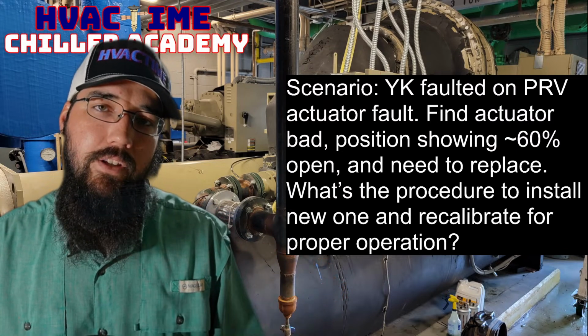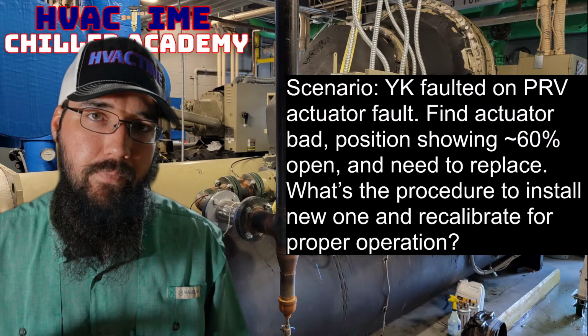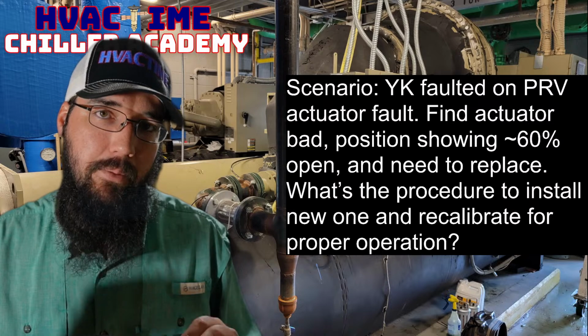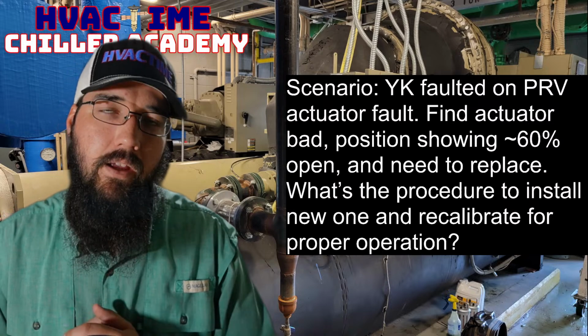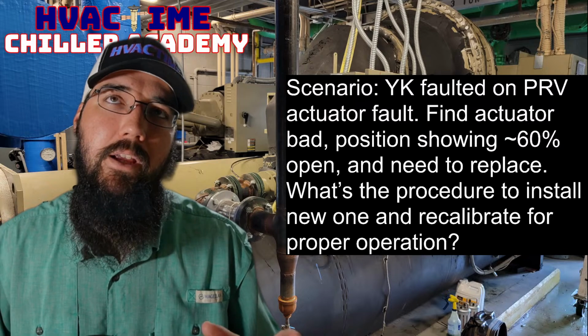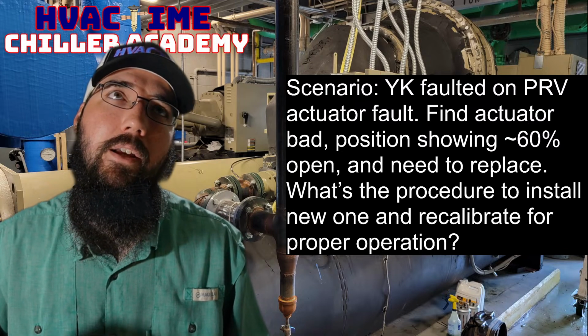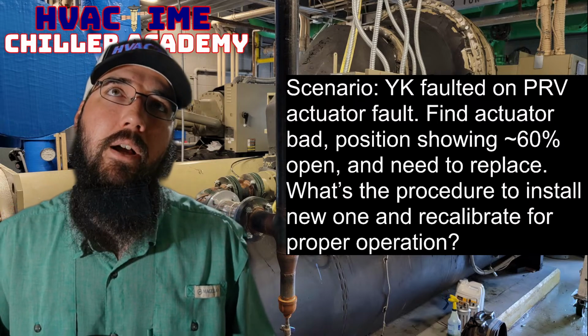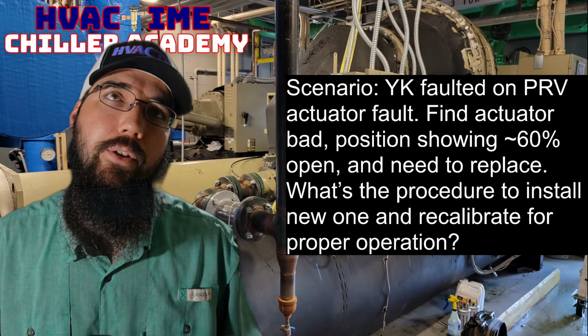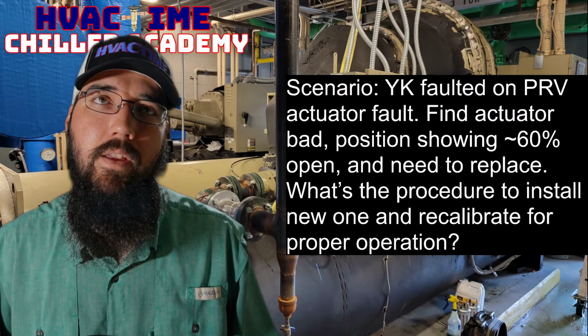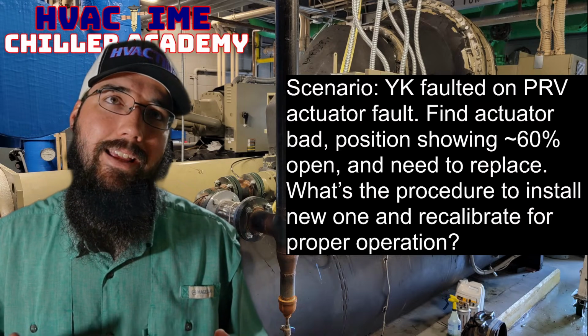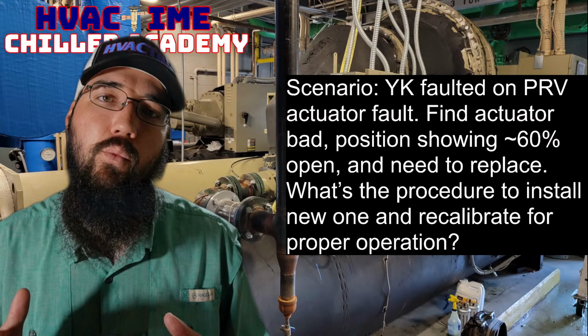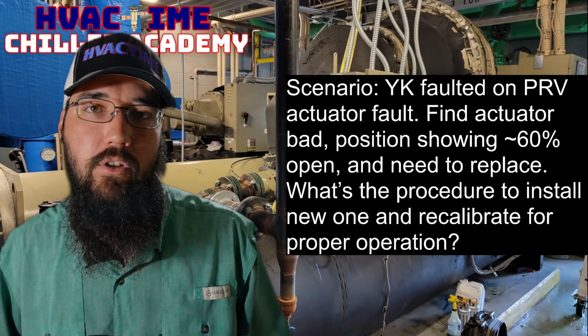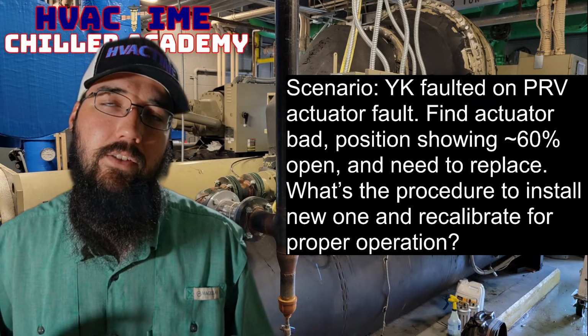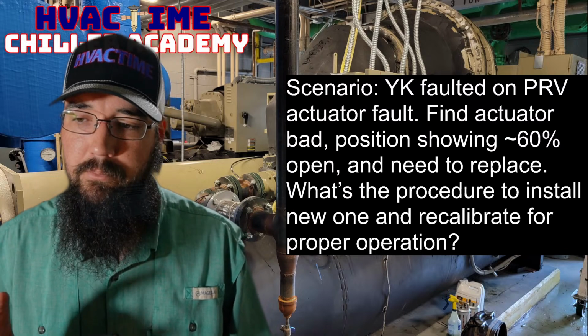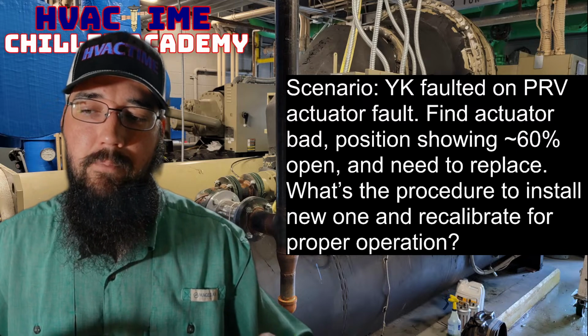It's important that the VGD be able to go to full open and get calibrated to that point so that it has maximum flow. When I've done mine, I've calibrated to full open instead of full closed, so I make sure I can get 100% diffuser gap whenever needed, and then I just close off as much as that 90 degrees will give me. So that would be one difference that's important here. I'm really glad you brought that up.